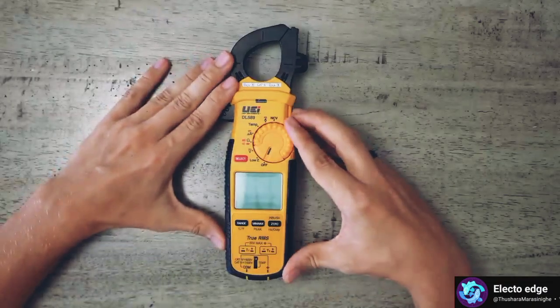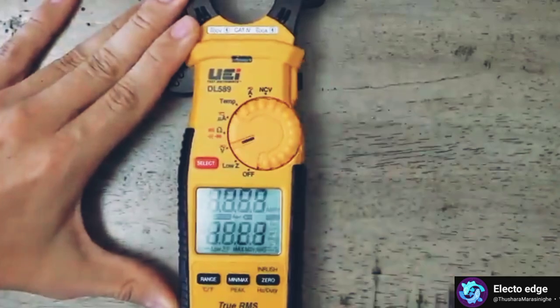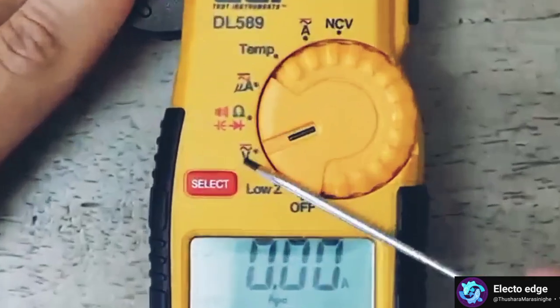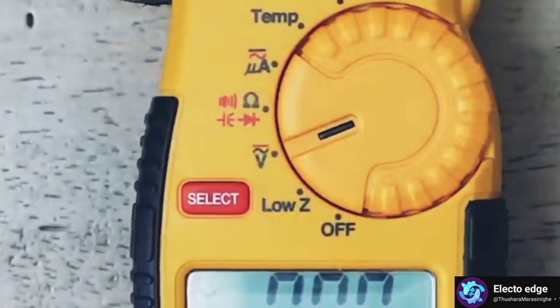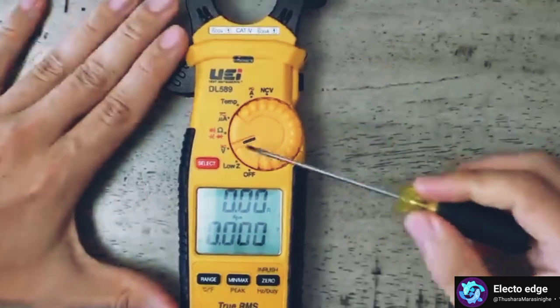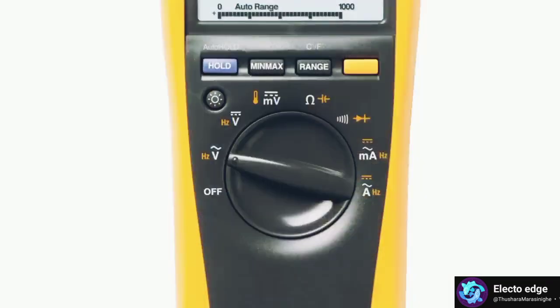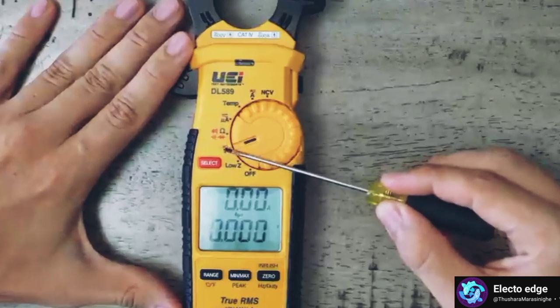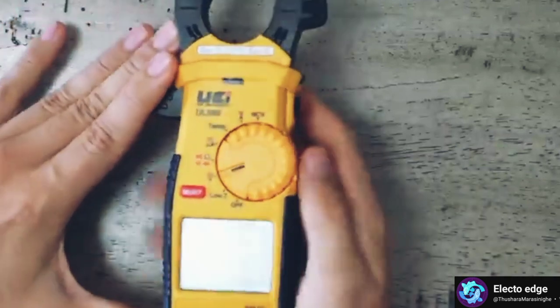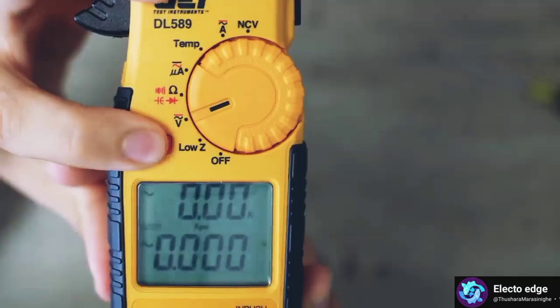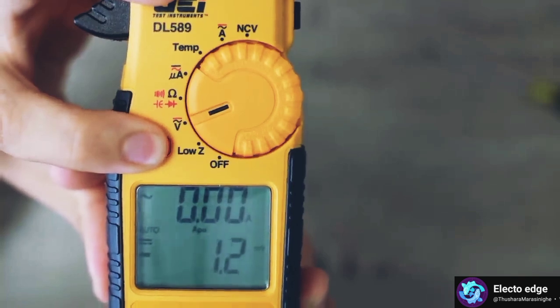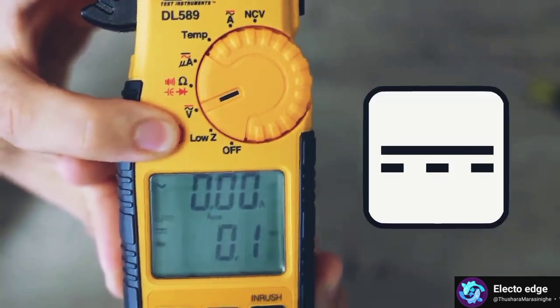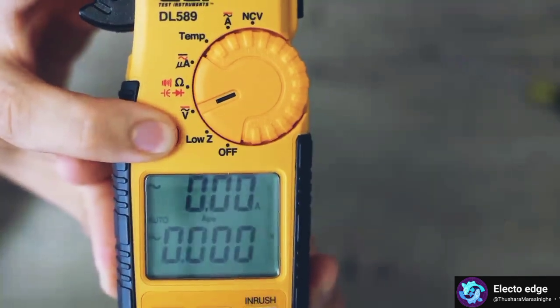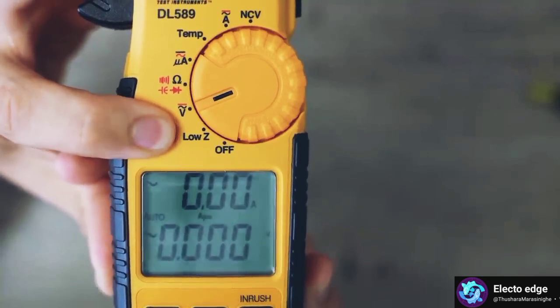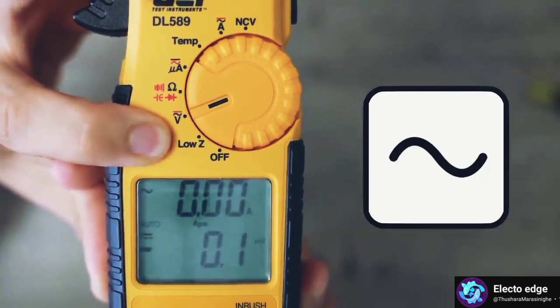To start things off, let's begin with voltage, which is represented by this letter V right over here. There's two types of voltages. There's direct current and alternating current. On some meters, they're going to be separated. There's going to be one for direct current and one for alternating current. But on this meter, they're both under one selection. And to change between the two, I would press this select button, which brings me to direct current. This symbol right over here, it's one solid line and dashed lines right under it. And if I press select again, it switches me back to alternating current, which is this wave symbol right here.